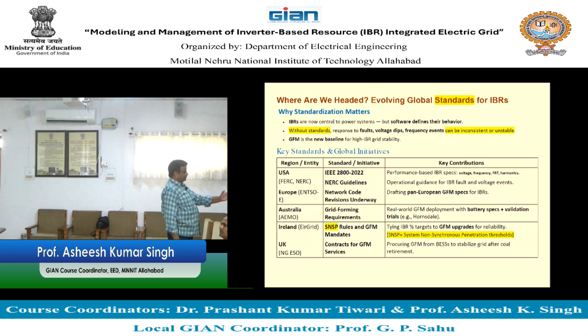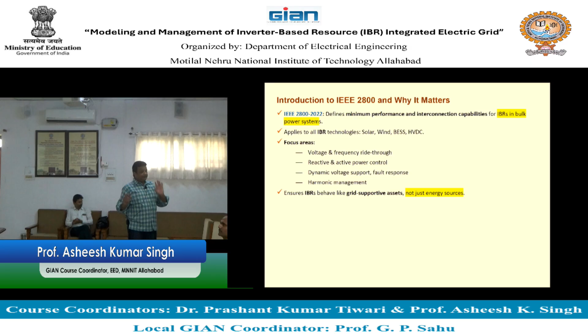So this is IEEE 2800 and why it matters. This defines minimum performance and interconnection capabilities for IBRs in the bulk power system. They are applied to all IBR technologies, means all sorts, right? And they are going to the limit of HVDC also. Focus areas are voltage and frequency ride-through, reactive and active power control, dynamic voltage support, fault response, and harmonic management. And they ensure IBRs behave like grid-supportive assets, not just energy sources. Means they are emulating the grid similar to the older version of the grid, with proper control, reliable operation with maintained stability.